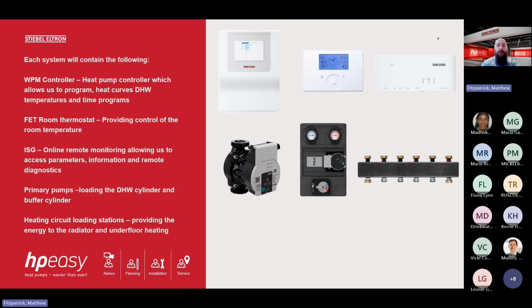It's crucial to get the pump size correct and also to ensure the pumps are efficient. So you don't want to install a very large oversized pump if you don't have to. And there is modern technology which is called PWM, so pulse width modulation, and this ensures the pump is operating at the correct speed. Now, you'll need to ensure that your heat pump manager or heat pump controller has the facilities to operate a pump via PWM. It is greatly beneficial. You can see up to 10 to 15% increase in efficiency on most systems with PWM pumps.